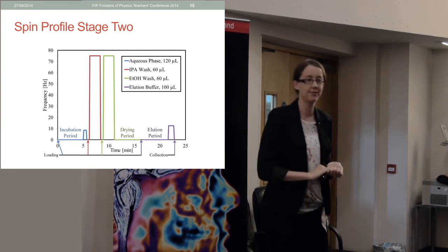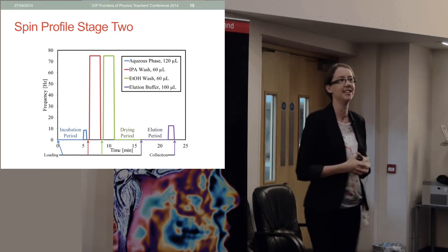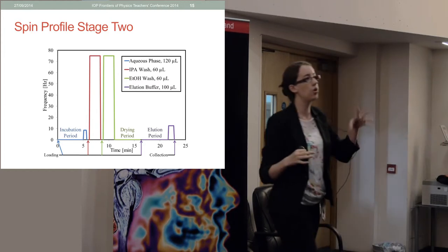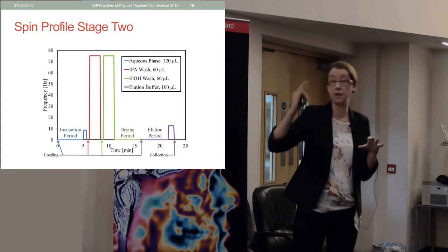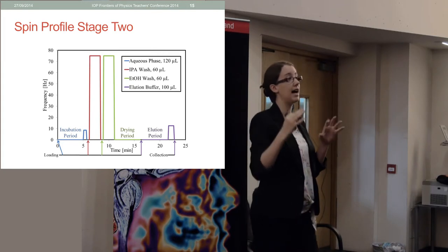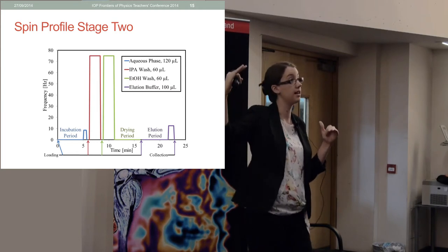Here's another graph. After initial loading there's a five-minute waiting period where the water solution is in contact with the beads, giving time for the RNA to bind. You then spin up and move the liquid along. The IPA and ethanol have to be spun very fast because they're not very viscous and they tend to want to travel over the siphon rather than through the hydrophobic membrane.